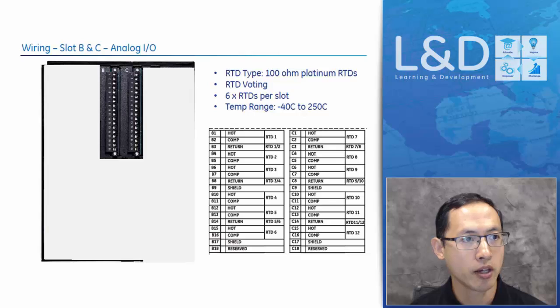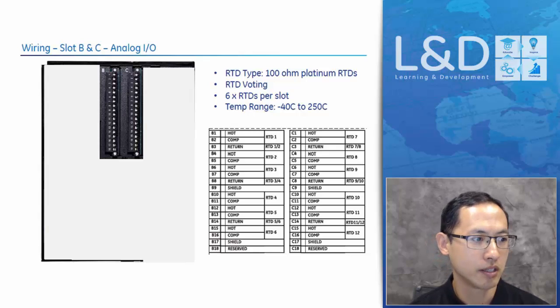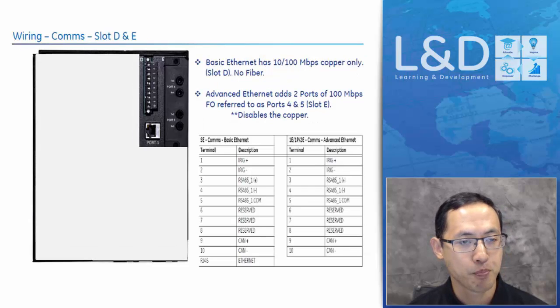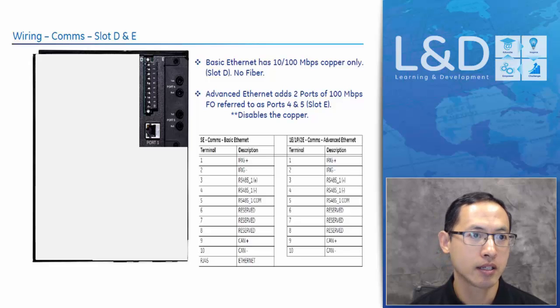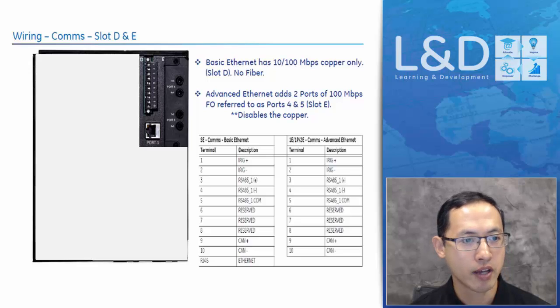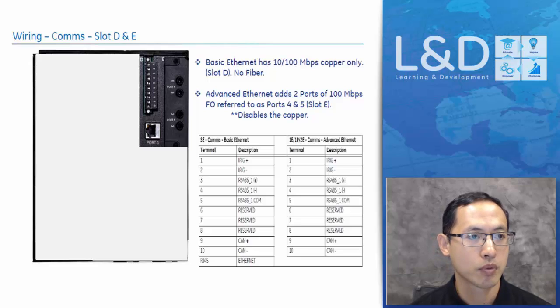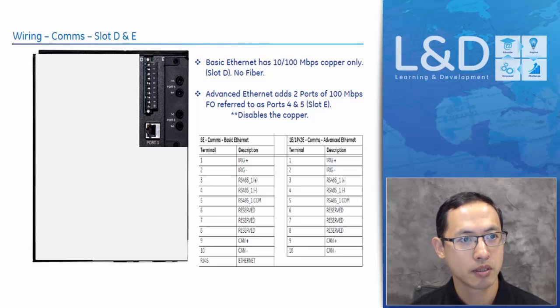In the low voltage I/O, which is used for the RTD and transducer inputs, one slot has 6 RTDs, and the measurement range is -40 to 250 Celsius. This RTD has RTD voting in the configuration, which means it has to compare its paired RTDs to make sure it's a valid RTD over temperature. And for the communication slot, there are basic communication and advanced communication cards. The basic one uses only the RS485 and the copper Ethernet. And the advanced communication card has two fiber optic Ethernet connectors.